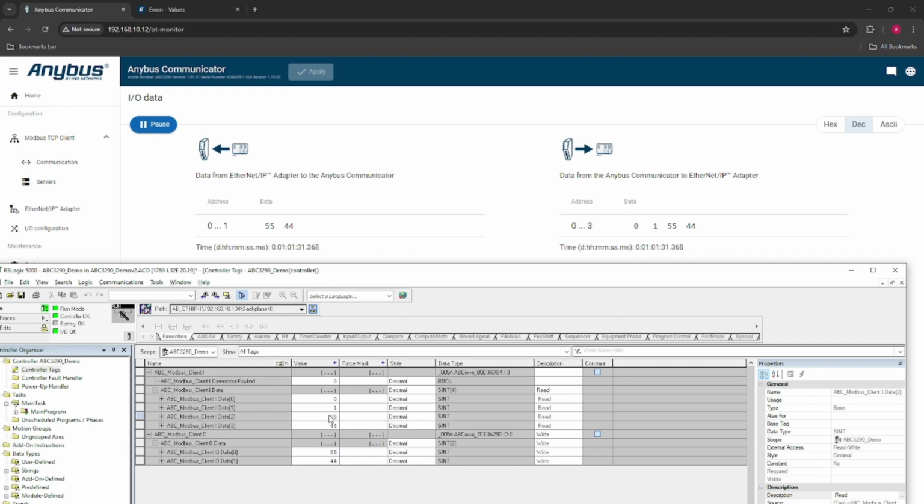It has written the 44 as well, and let's just say if it goes offline, you'll see it has entered the safe value which we entered before. Just turn it back on, it should return to normal. Yep, great, it's returned back to normal. So let's just see. We'll just turn it back off, and let's try entering a new number, see what happens. Nothing happens, and we'll just turn it back on and enter the new value as well.